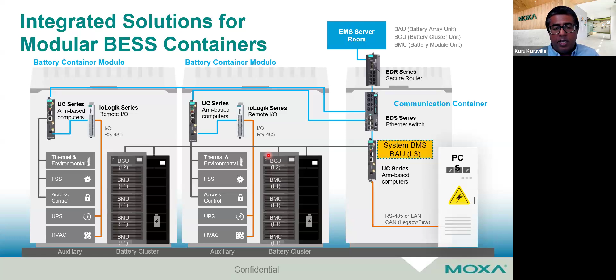And then you have to keep doing it at scale, right? Because most energy storage systems will have multiple banks of batteries. So if you have to repeat the setup every time, that's not the best use of time. You need tools and devices that enable fast configuration, automatically detect the devices in the system, automatically assign IP addresses, and have switching and routing that is expandable, so when you add the next block, you have enough capacity to expand.